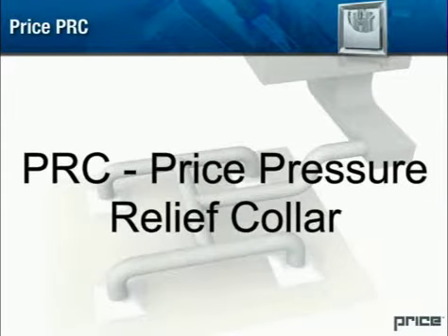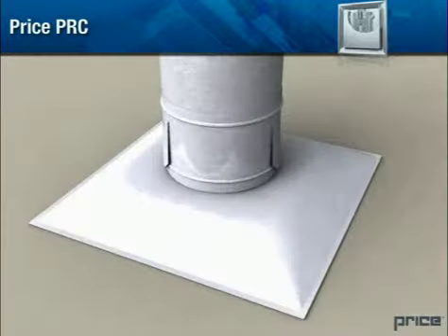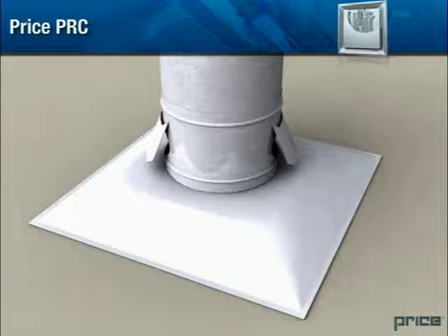PRC, Price Pressure Relief Collar. Price pressure relief collars are a simple mechanical way of controlling system pressure. These collars have bypass gates that are forced open by a predetermined system pressure. When they open, air is bypassed into the ceiling plenum, thus reducing the pressure in the duct.